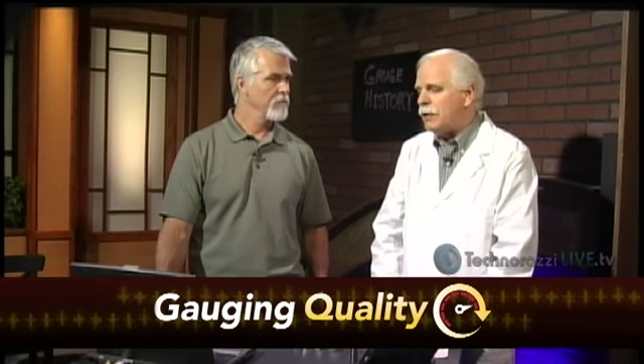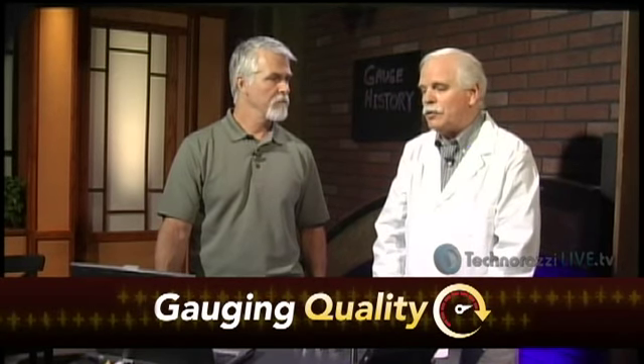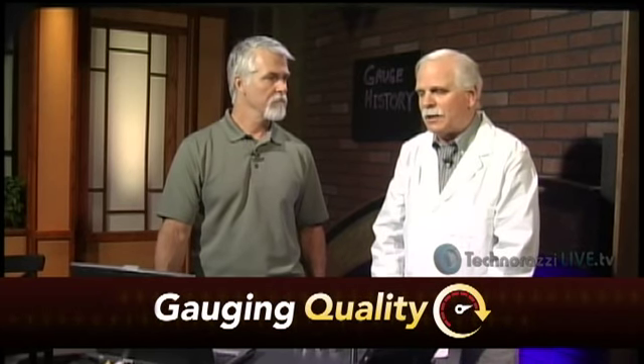Everything was fine. At 300, it'd blank out. So we actually had a limited calibration, do not use over, I forget where the limitation we put on it was, 280 grams, something of that nature.